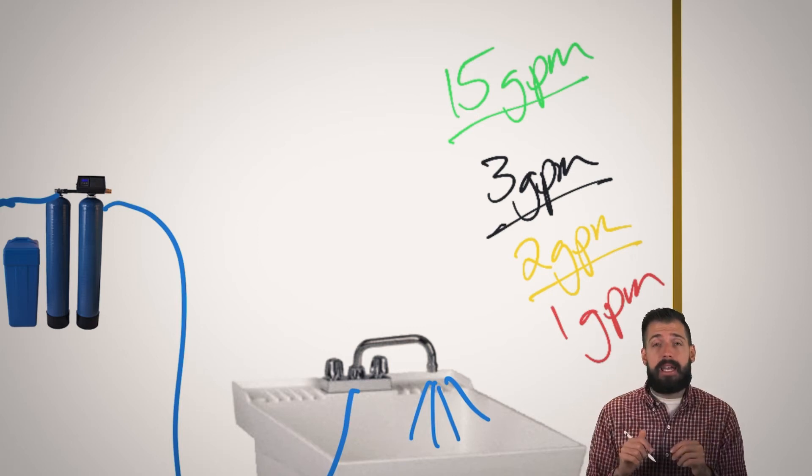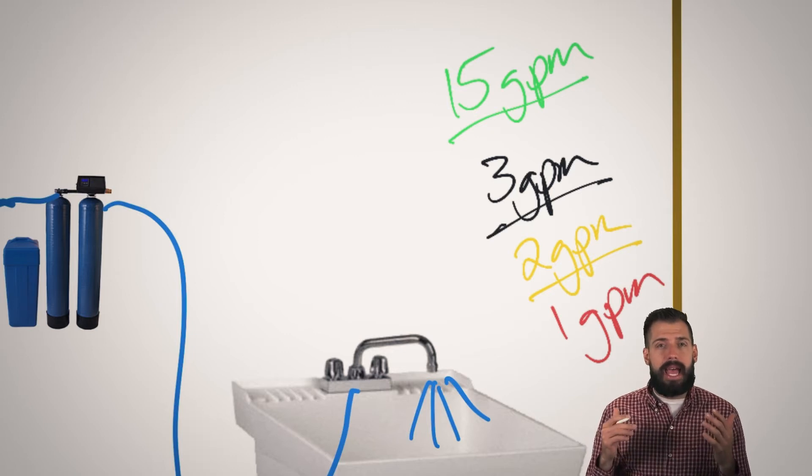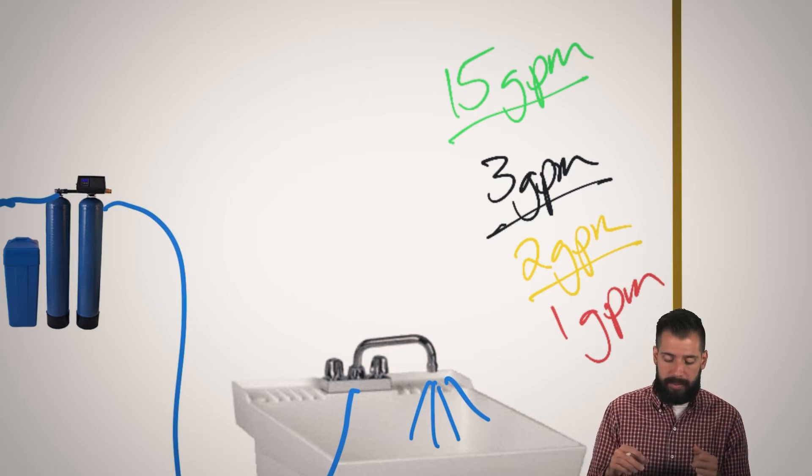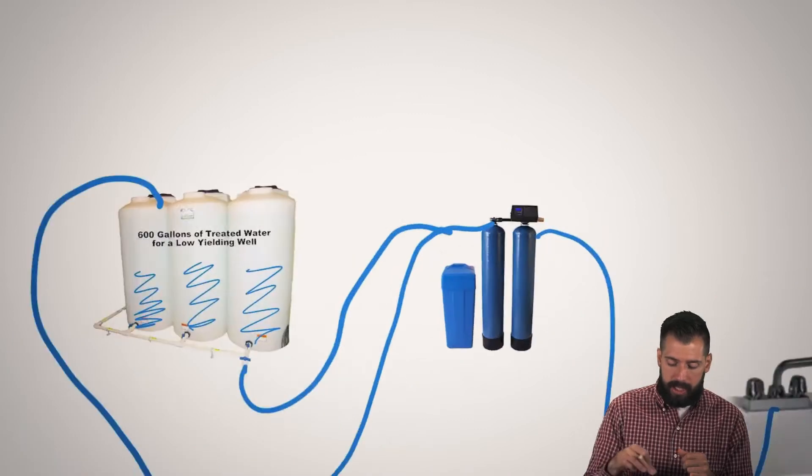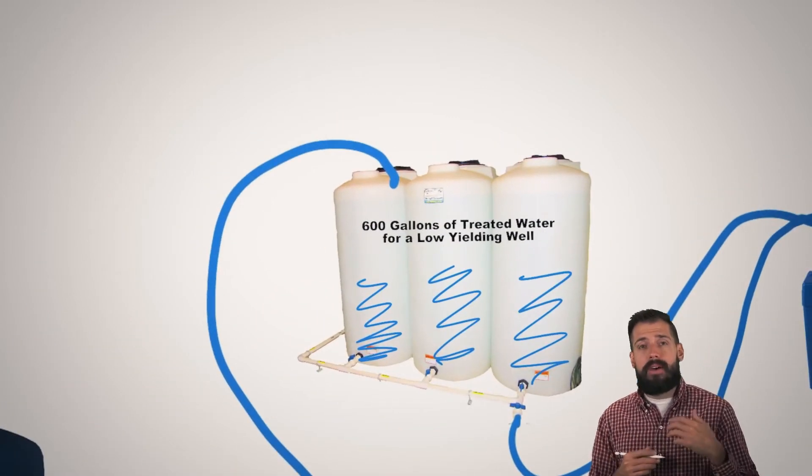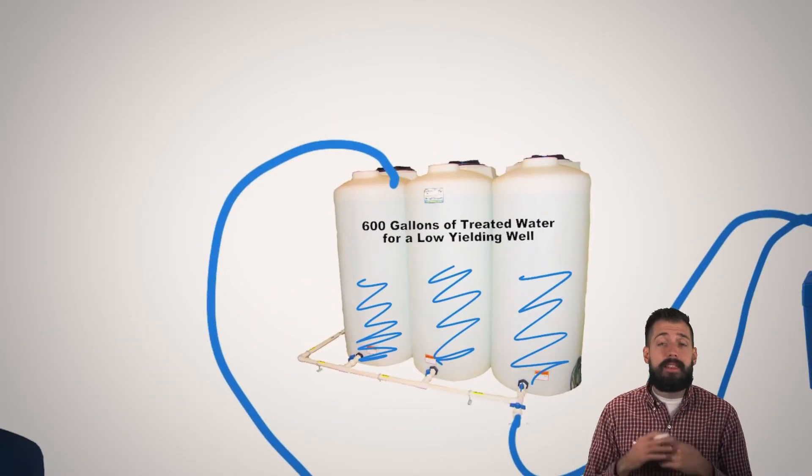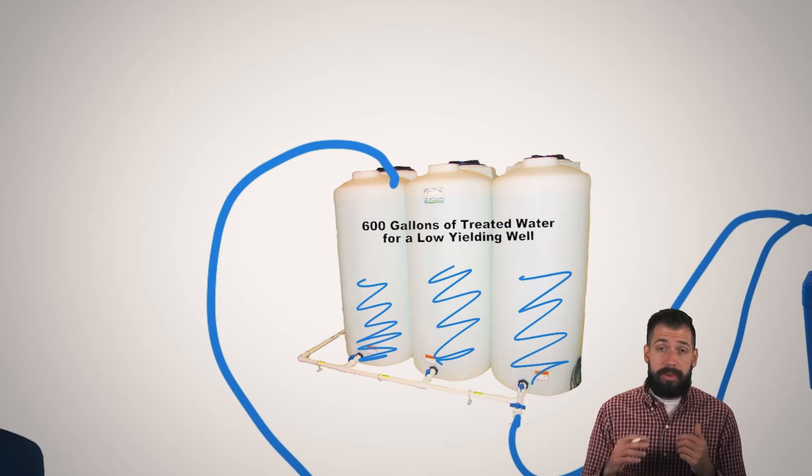Well, let's say we pass the test by hitting two hours, but we were only at two gallons per minute or one gallon per minute. Well, then our recommendation would be that you get some kind of water storage system. So that way you have that water on demand as you need it. That would be our recommendation.